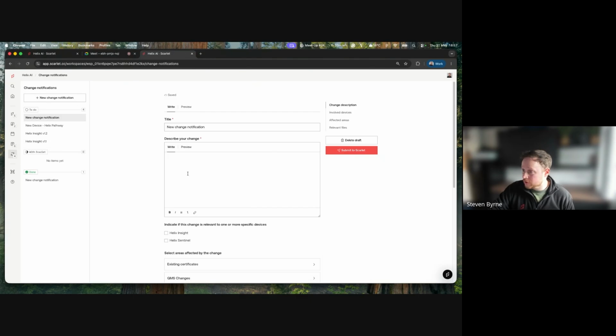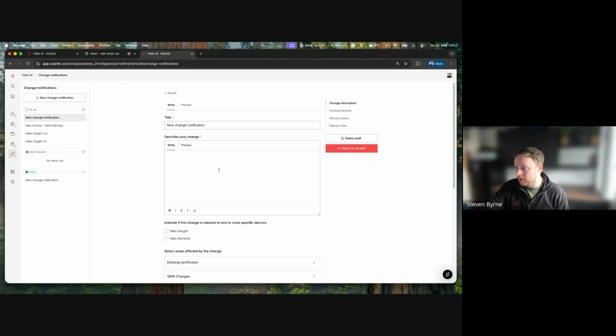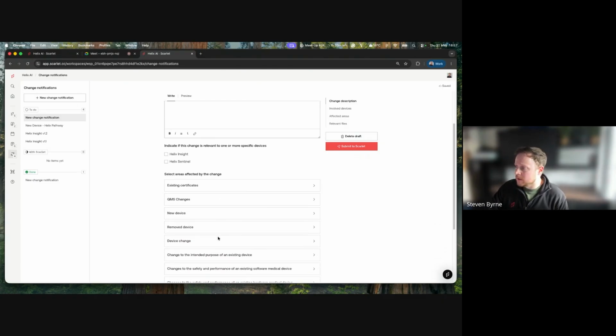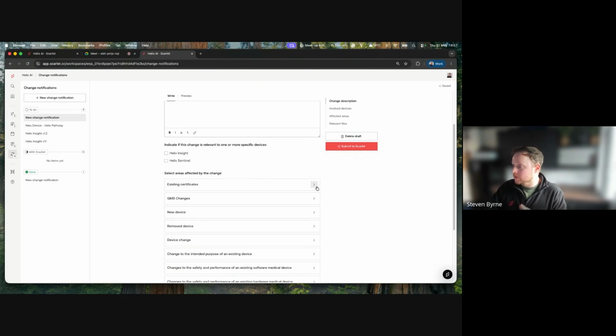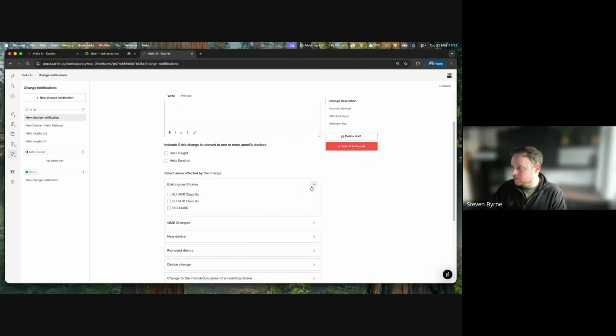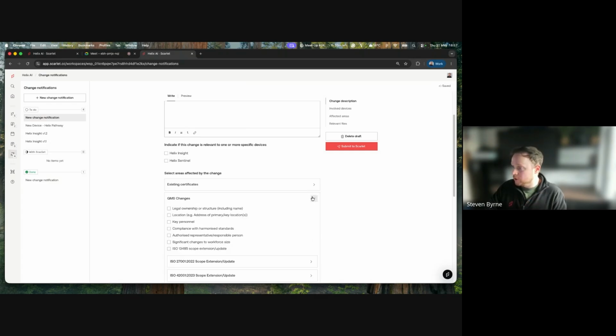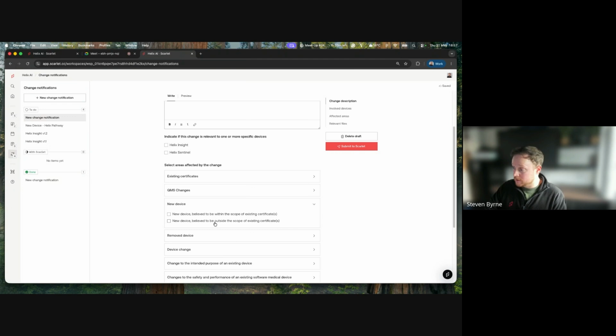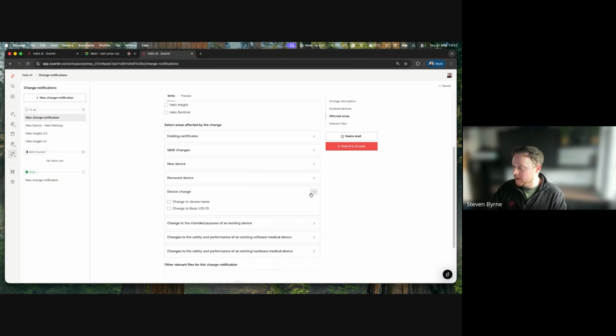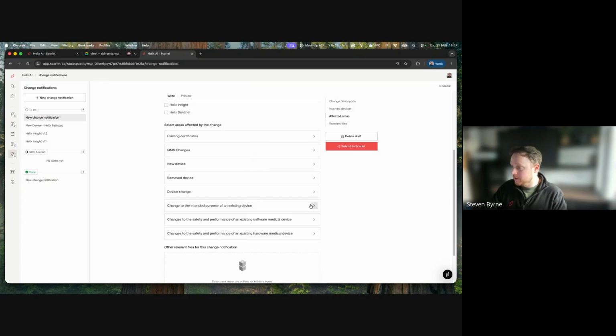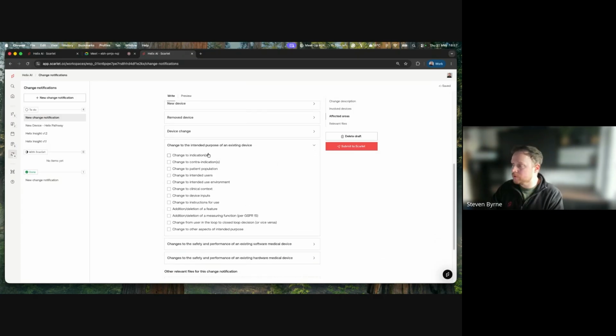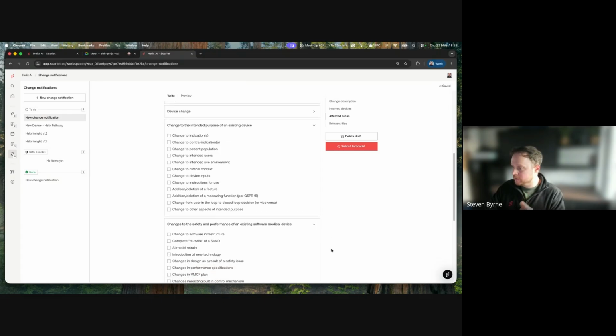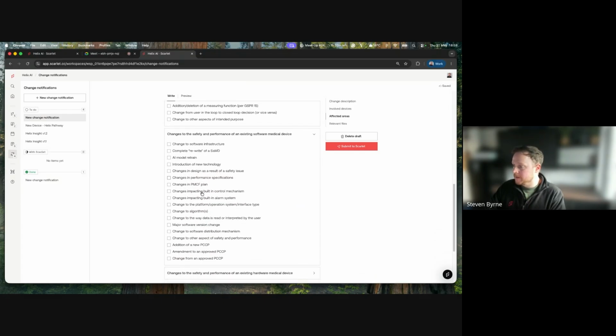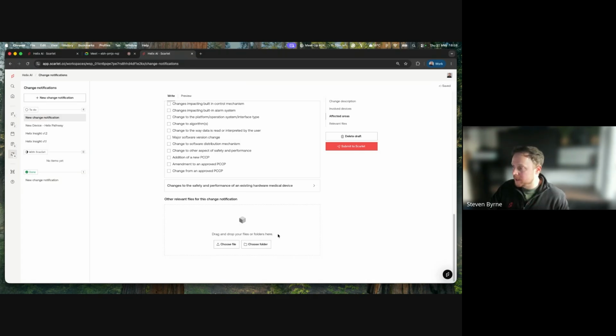So this is just the title of the change, and the description, giving us a brief description of exactly what it is you're changing. And then underneath, we've got a selection of boxes that you can select. So you can tell us whether it's specific to a device you already have. We can drop into whether you think it's changing an existing certificate that you have, whether it's a QMS change, whether it's a new device inside or outside the scope, and further down, device changes, maybe a change to the device name or the UDI. And then here's where more detail comes in: how the intended purpose of the device is changing. Is there any change to the safety and performance of the software? And at the bottom, you can drag and drop files in that help provide clarification on exactly what it is you've changed.